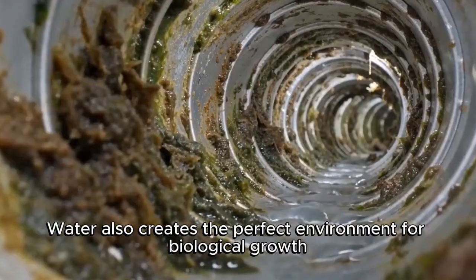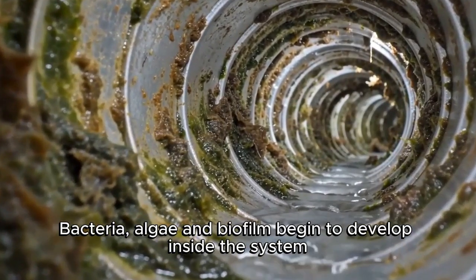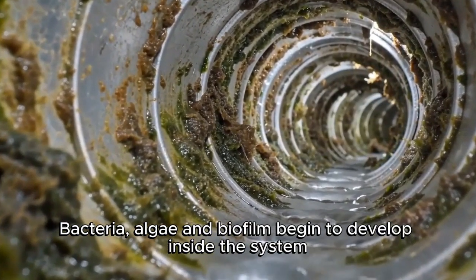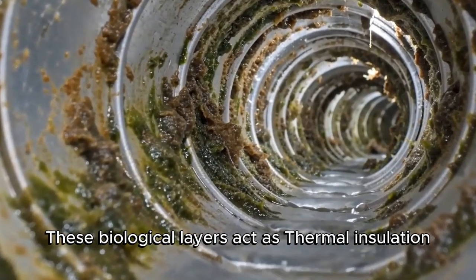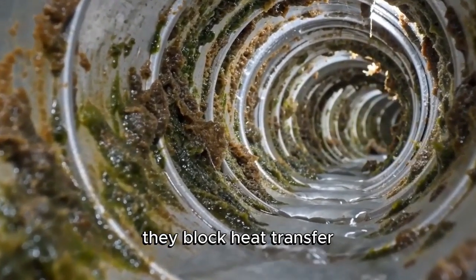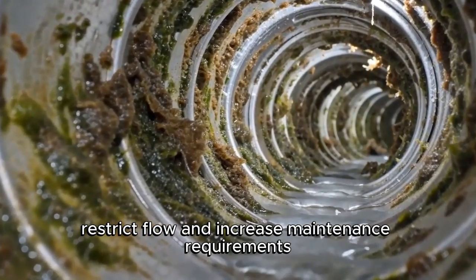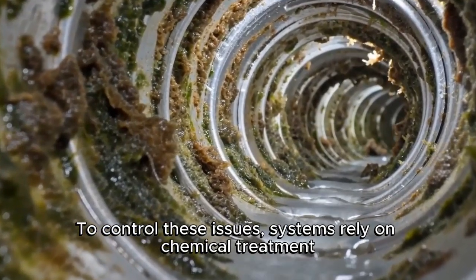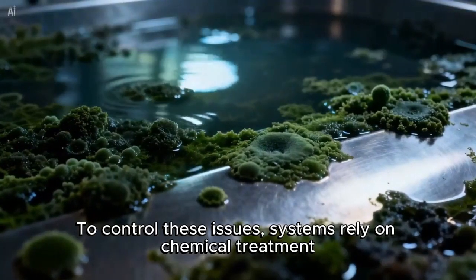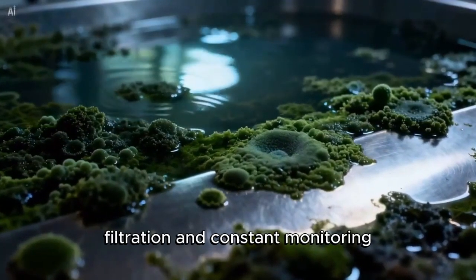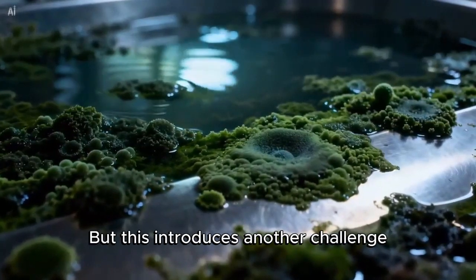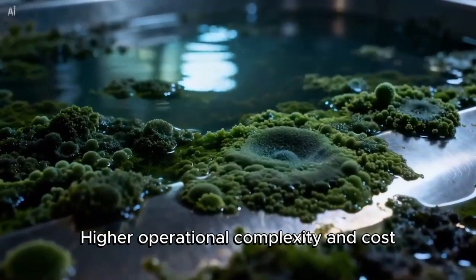Water also creates the perfect environment for biological growth. Bacteria, algae, and biofilm begin to develop inside the system. These biological layers act as thermal insulation. They block heat transfer, restrict flow, and increase maintenance requirements. To control these issues, systems rely on chemical treatment, filtration, and constant monitoring. But this introduces another challenge: higher operational complexity and cost.